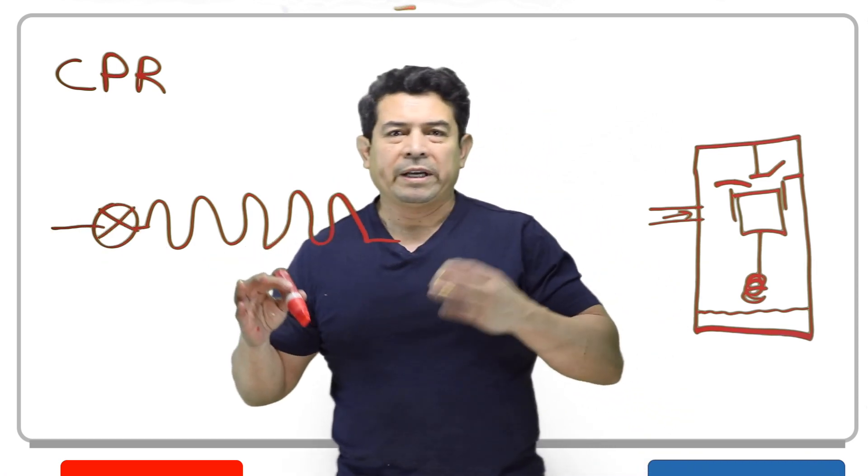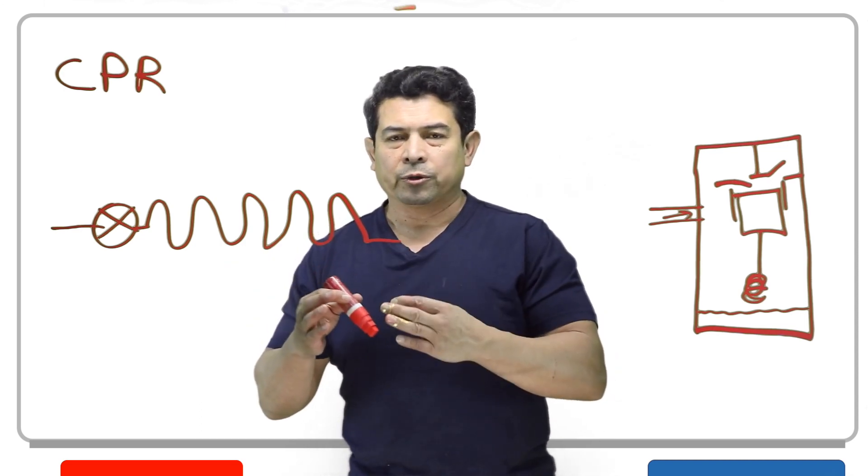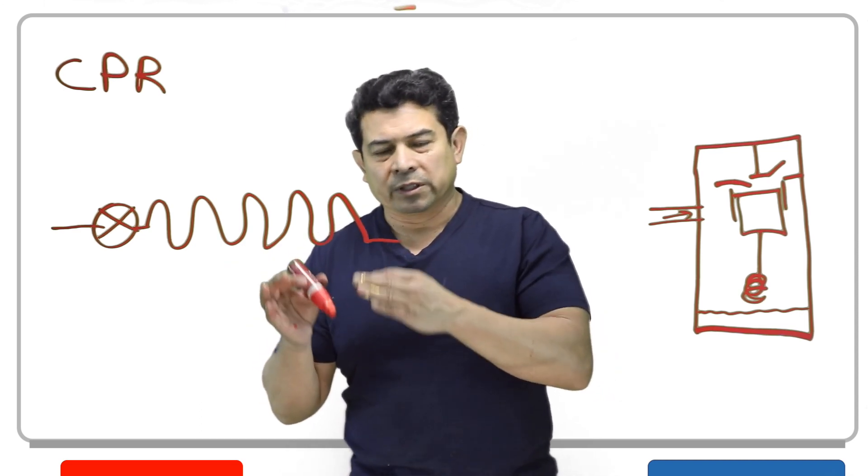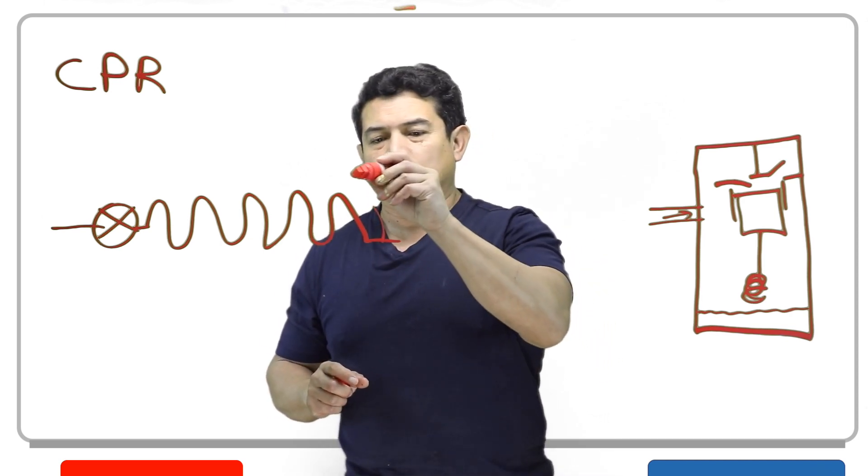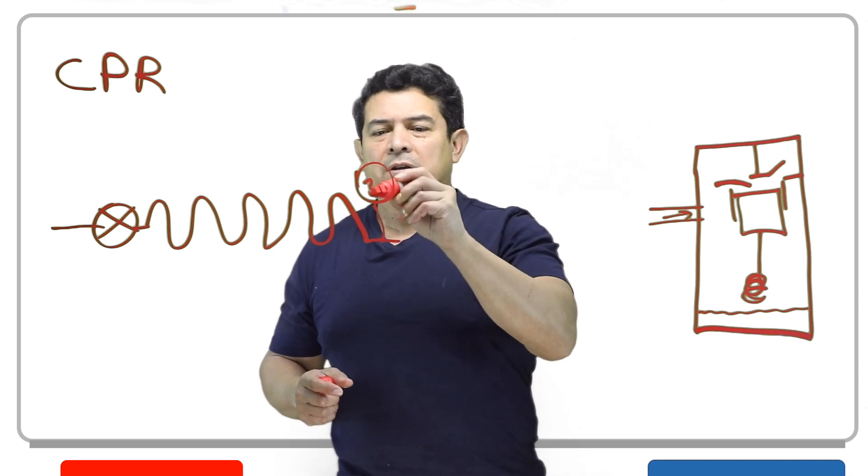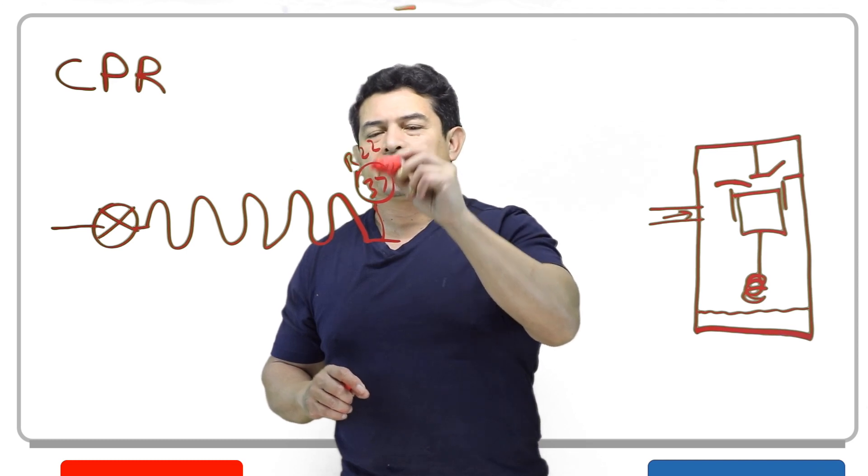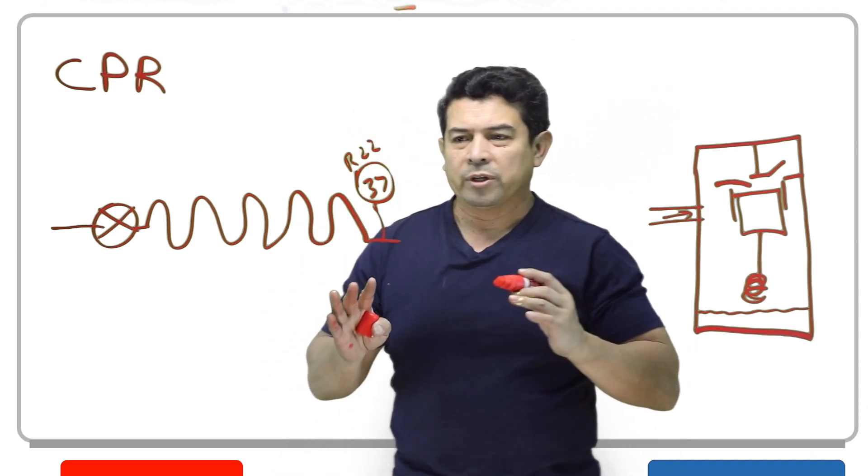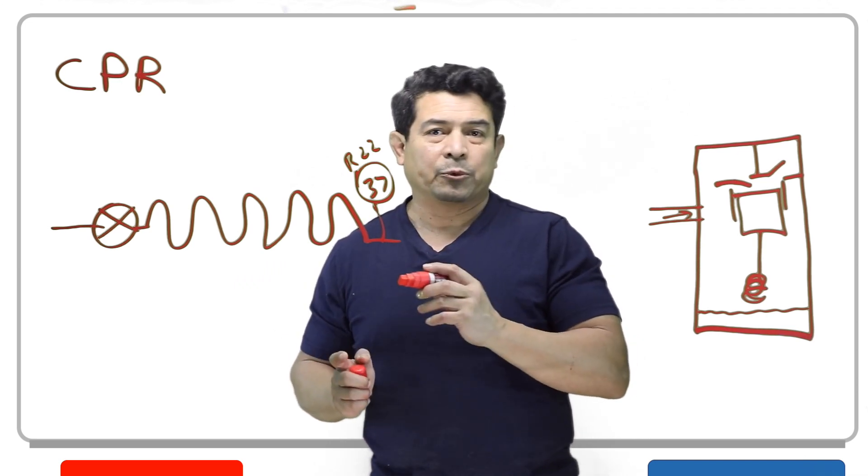This evaporator is going to be at a specific temperature. Now the temperature, we know what the temperature is going to be because of the pressure. So we can have an actual pressure gauge here. And let's say this reads 37 PSIG. Let's say that this happens to be R22. The point is that that pressure is going to tell you what the temperature of the evaporator is.